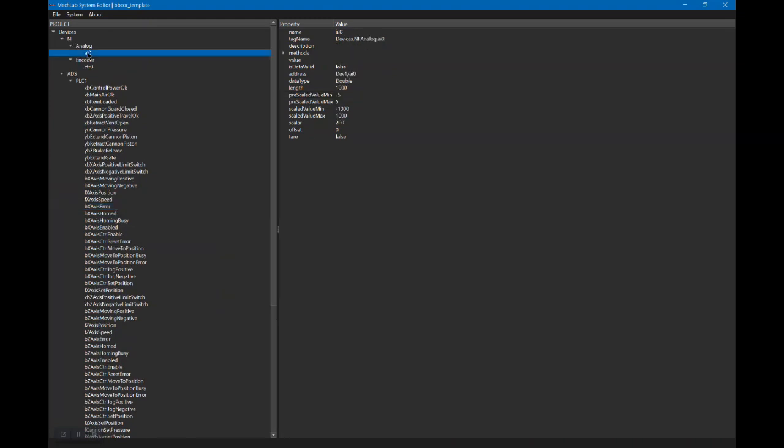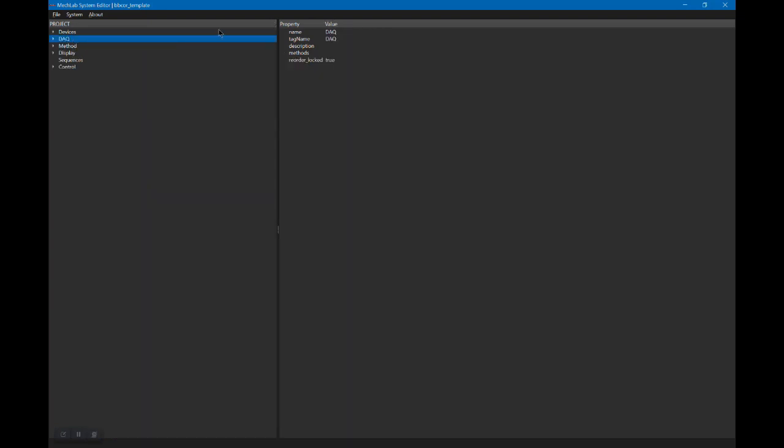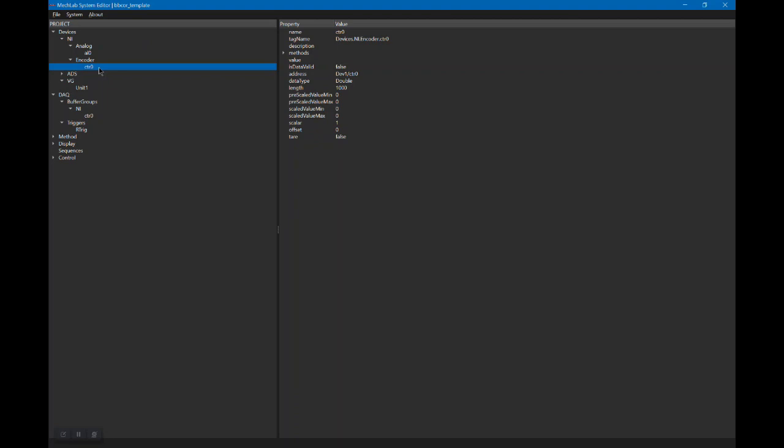Well, here's a good example here. We put in a pre-scaled value, an engineering value here, and a scalar and an offset are calculated. DAQ stands for data acquisition. Once the data comes in from the devices, we want to put it into software buffer groups. In this particular case, we have a buffer group recording from counter 0, which is a channel defined over here. You'll notice this tag name here, and we have the matching tag name here. Every item in the tree gets a tag name that allows you to identify it and reference it from anywhere else in the project.